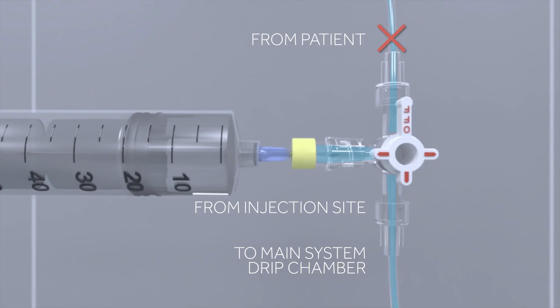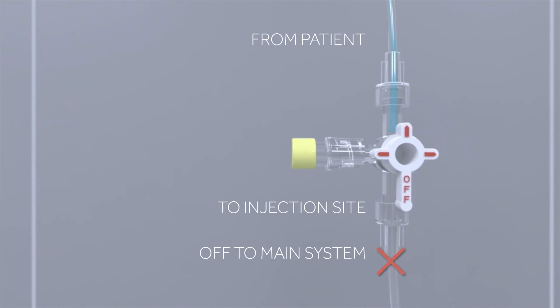This might be done to flush an obstruction in the patient line towards the drip chamber. With a stopcock in this position, no fluid from the sampling site will communicate with the patient. Finally, if the stopcock is rotated OFF to the main system, fluid can flow either from the patient's catheter to the sampling site or from the sampling site towards the patient's catheter.